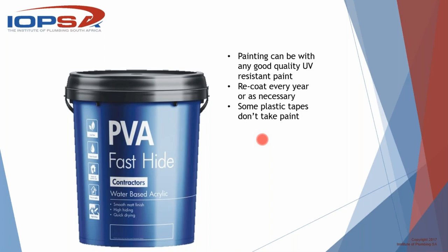And don't kid yourself. One coat of mediocre or cheap paint does not constitute protection. You've got to make sure that the thing's protected. You'll see a picture in the next slide where the thing was painted, but it's as if it wasn't. So 2-3 coats of good quality PVA. I want to tell you that with 100% acrylic PVA, you put a coat on some lagging now, and by the time you get to the other end of the installation, where you started is dry already, and you can go back immediately and put a second coat on, no problem. So you can do two coats while you're there. You don't even have to wait between coats. And if it's proper paint, nice and thick, you've already done probably a year's worth of painting, and you only need to recoat again in about a year.